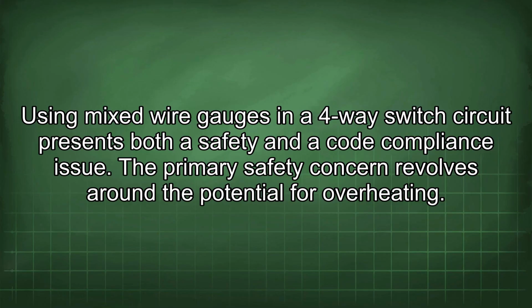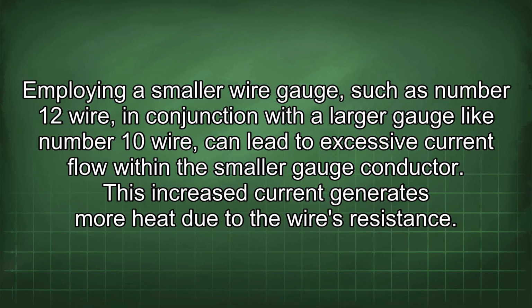Using mixed wire gauges in a four-way switch circuit presents both a safety and a code compliance issue. The primary safety concern revolves around the potential for overheating. Employing a smaller wire gauge, such as number 12 wire, in conjunction with a larger gauge like number 10 wire, can lead to excessive current flow within the smaller gauge conductor. This increased current generates more heat due to the wire's resistance.